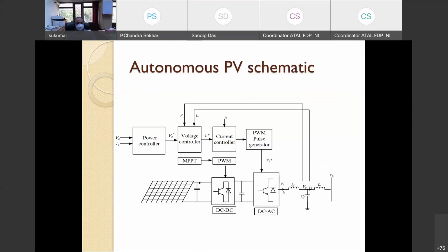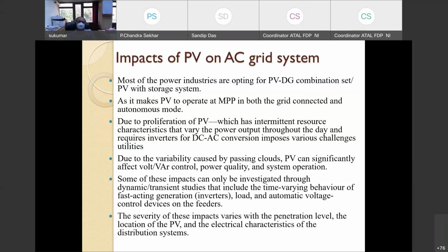So this is autonomous mode, I am leaving it. So when you do this grid connected system, then you will have certain amount of issues while sending the current to the grid. And that is mainly because of the impedance of the feeder line. So when there is a line, that line will have some resistance and inductance, and that will create problems for the injection of current from the inverter to the actual grid.